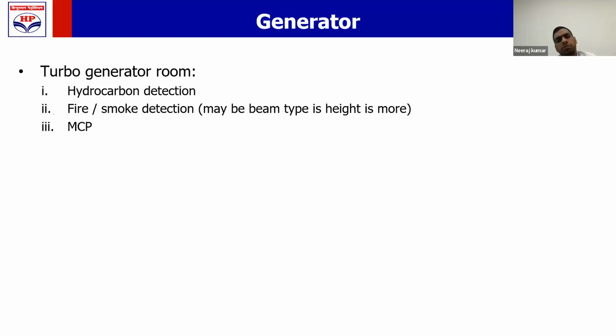Sometimes if the height of your generator room is quite high, I have seen generator sheds of height 18 meters or even up to 20 meters. In those cases, the fire and smoke detectors may not be able to serve the purpose because the concentration of smoke generated may not reach those detectors in sufficient quantity. So in those cases where the height of the turbine generator room is quite high, then a beam type fire detection system may be installed, which works on the principle of light reflection.